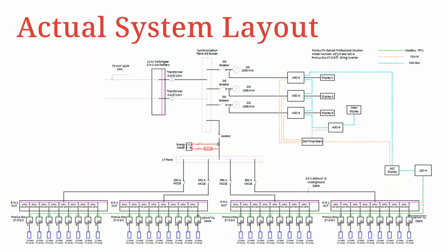In this system, it's got a genset integration, so it's using a DEIF controller. Here it's using a display unit for the DIVE, and then the communications. It's using Modbus RTU, for example, from the controller itself, then communicating to each inverter via Modbus RTU, so it's RS485. Whereas the TCP connection is then from the DEIF to its separate controllers, and also the CAN bus. This is just a typical example of an SLD that will be required at each individual site.